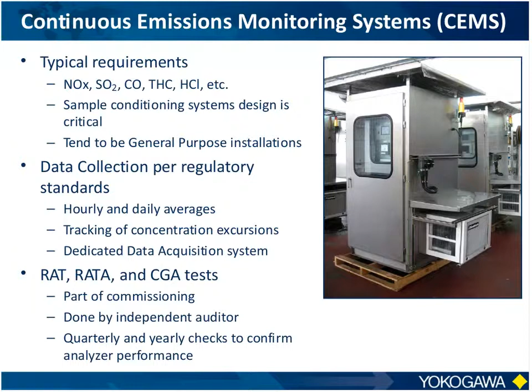There's also typically relative accuracy tests, accuracy audits, or cylinder gas audits involved as you install the equipment. These are part of commissioning and ongoing operation to prove the analyzer system actually works and is accurate to a relative degree. Most system integrators, directly or through third-party partnerships, can assist in making this happen so the equipment can be started up and certified, if you don't already have your own sources from past experience.